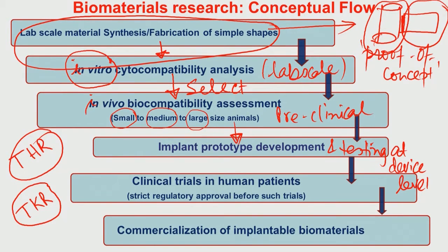So, once a large number of fatigue cycles are conducted using this hip simulator and the materials survive, the materials do not fracture, they do not wear to a significant extent, and their wear debris particles are taken and their non toxicity at cell or tissue level has been established, then only all these preclinical test results are further transferred to the next level of study, that is called clinical trials.